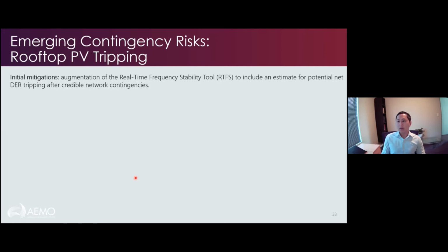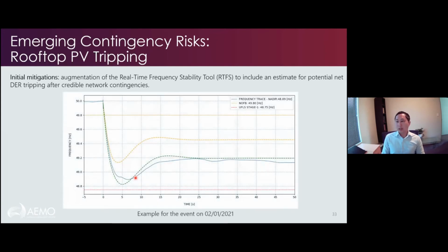And that caused frequency to deviate. And so what we've done since then is we've had to augment the RTFS tool to include an estimate for the potential amount of DER tripping after these sort of credible network contingencies. And so here's a graph from the day. This is the event. This is what was measured on the day.